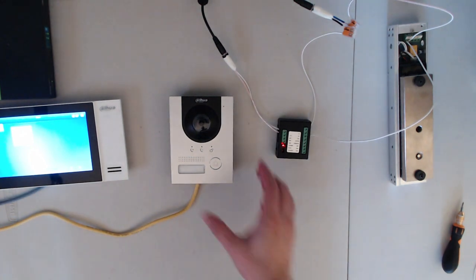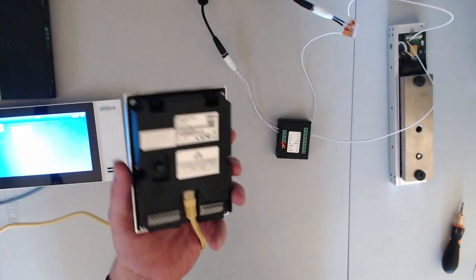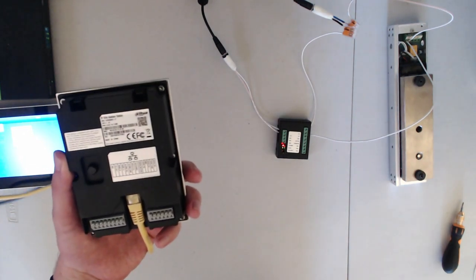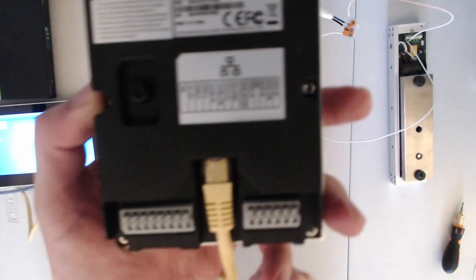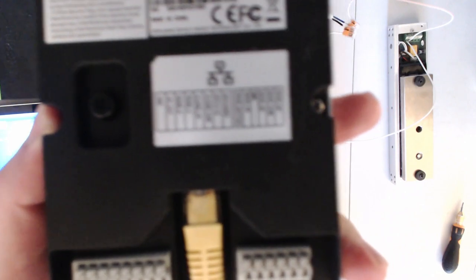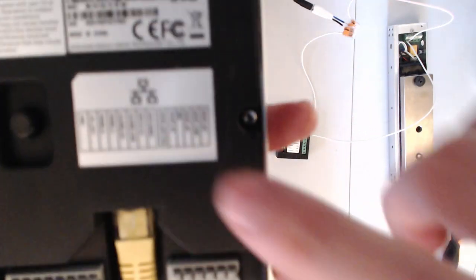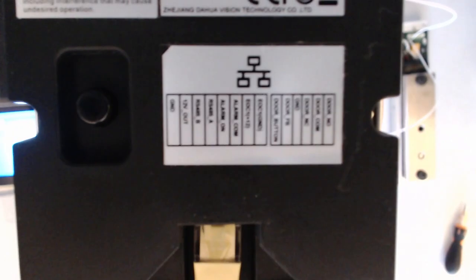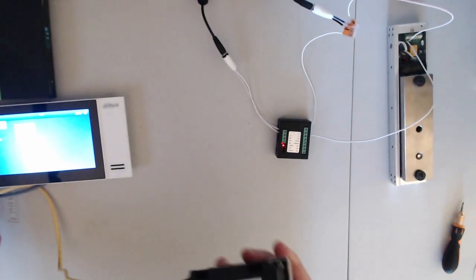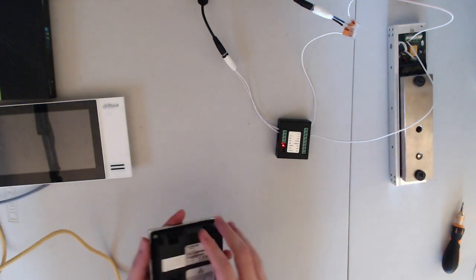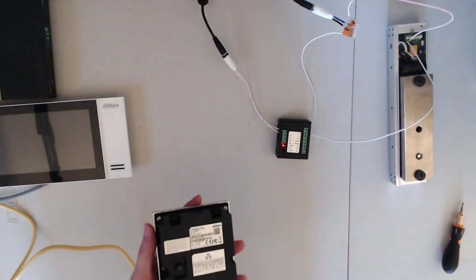We're going to go ahead and start wiring the RS-485 directly from the back of the VTO to our extension module. On the back of the VTO, we have our two connections for the RS-485. We have our A and B. Now, depending on the model VTO, sometimes you would need to wire it from A to B and B to A. But for this particular VTO, it actually requires A to A connection and B to B connection. I'm going to go ahead and do that now.